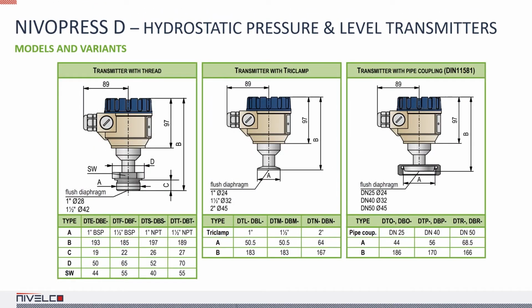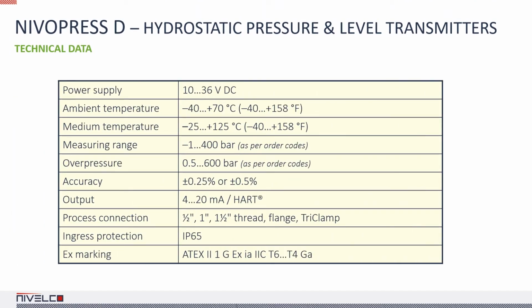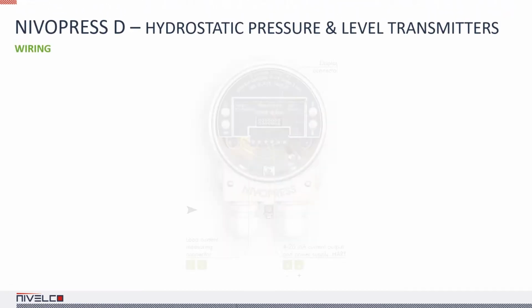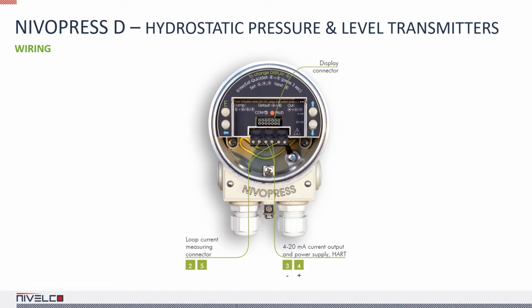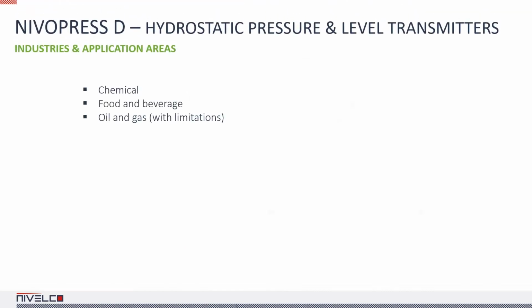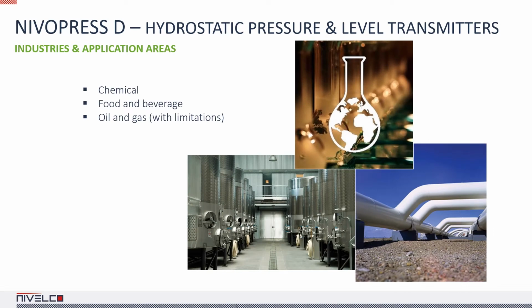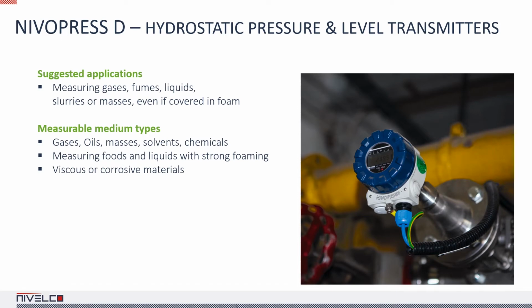The NIVOPRESS product family can also be used in food applications. The devices are available with a threaded, tri-clamp, or DIN 11851 process connection. Due to the capillary, the ingress protection of the device is rated IP65. The loop current can be measured with a multimeter on the terminal block. The oil and gas industry uses the NIVOPRESS in storage tanks. These devices can be used even if the tanks have built-in stirring blades. The devices can be used for measuring gases, fumes, liquids, slurries and masses, viscous and corrosive materials, foods and liquids even if they are covered in foam.